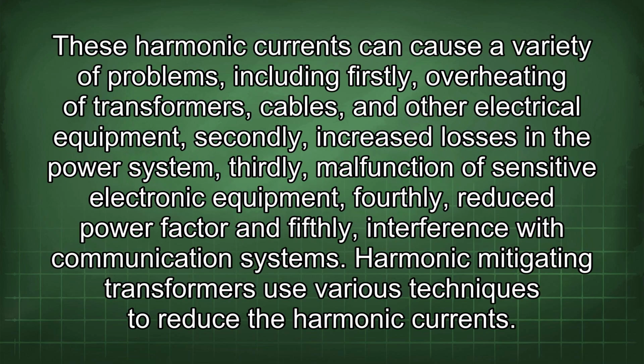These harmonic currents can cause a variety of problems, including firstly, overheating of transformers, cables, and other electrical equipment. Secondly, increased losses in the power system. Thirdly, malfunction of sensitive electronic equipment. Fourthly, reduced power factor. And fifthly, interference with communication systems.